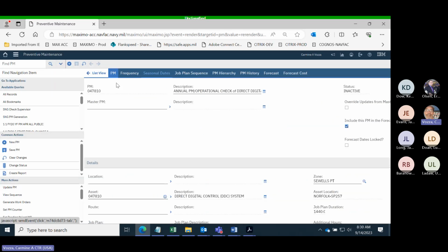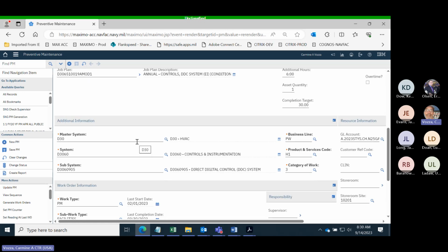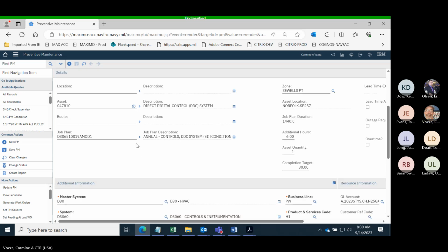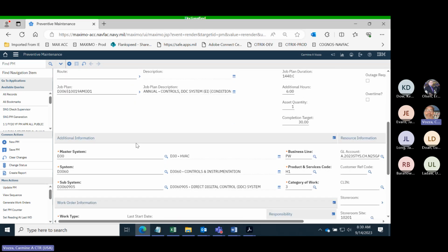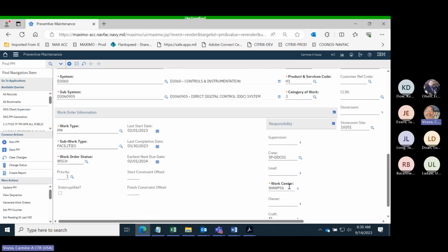Each work center has the opportunity right here to either select it or drop out. We definitely encourage all the FECs to pick one, because if you don't want to use it, you just don't check any of your work centers. Later, you can activate that work center and the AutoGen will work. So for this work center, WAWPS6, every evening Maximo goes out 14 days and generates the work. The technician comes in and sees all my PMs are out for 2 weeks, carry on.